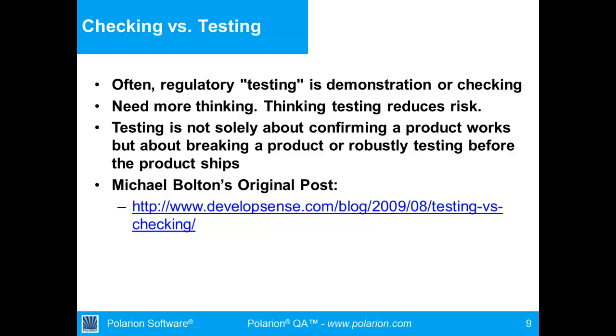Griffin, that makes me think of something. In a regulated environment, a lot of times there's a document that people outside of regulation I don't think are familiar with at all, known as a traceability matrix. So you might have a requirement, you then map it to a test case to prove that you've tested that requirement. So I would imagine a question might be, well, if I leave my scripted test cases, how will I be able to prove it? And I don't see any issue why your traceability matrix couldn't point to an exploratory testing charter. Absolutely. And handle the mapping there. I've done it in the past multiple times.